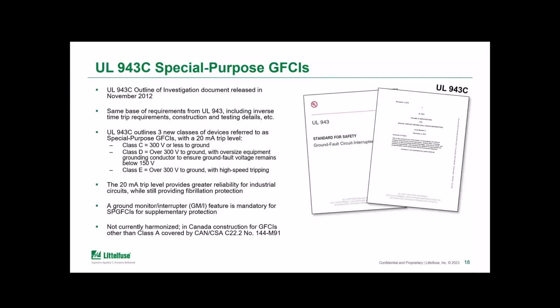So UL recognized that demand, and we'll say opportunity, for GFCIs to also be able to protect at 480 volts and 600 volt, and with trip levels that could perhaps accommodate some of that industrial equipment that had slightly higher leakage levels. So about 10 years ago, the UL 943C document was released for special purpose GFCIs. If you've ever downloaded the document, you can see it's labeled as an outline for investigation. And that's because it's a first release document that hasn't gone through the same UL standard release process, but product can still be listed to this document just as any other standard.